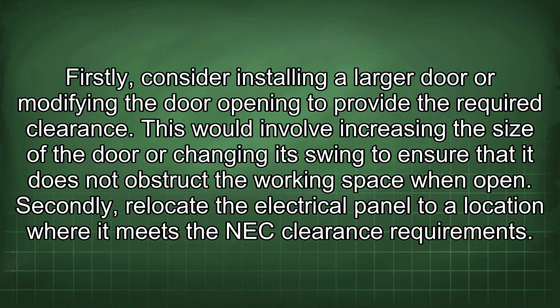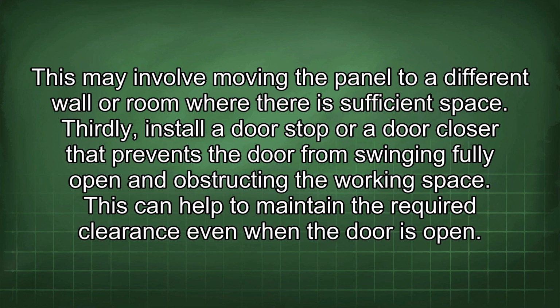Firstly, consider installing a larger door or modifying the door opening to provide the required clearance. This would involve increasing the size of the door or changing its swing to ensure that it does not obstruct the working space when open. Secondly, relocate the electrical panel to a location where it meets the NEC clearance requirements. This may involve moving the panel to a different wall or room where there is sufficient space. Thirdly, install a doorstop or a door closer that prevents the door from swinging fully open and obstructing the working space. This can help to maintain the required clearance even when the door is open.